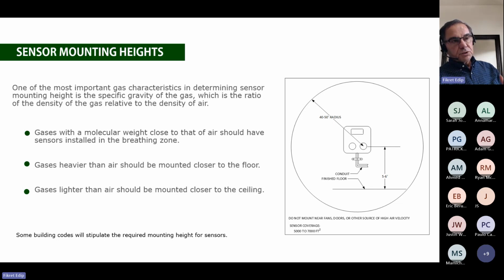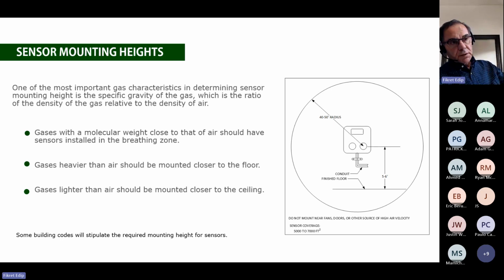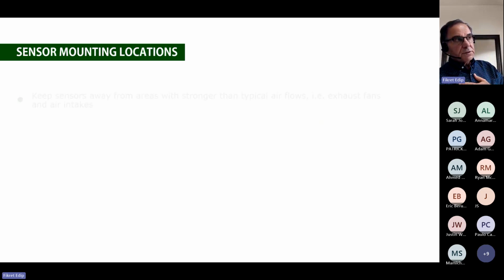Why? Because the refrigerant gases are so heavy, it takes a lot of air movement to move them for the sensor to detect them, and therefore we mount the refrigerant sensor near the leak source and at a maximum of 12 inches above finished floor. But as a rule of thumb, in general, the sensor coverage is a 40 to 50 foot radius, application dependent. And the mounting height, which I illustrated here: you look at the air density. If it is heavier than air, obviously it goes 12 to 16 inches above finished floor. Same or close to the air density, then you will be mounting at 5 to 6 feet, and much lighter gases like hydrogen and methane can be mounted near the ceiling.